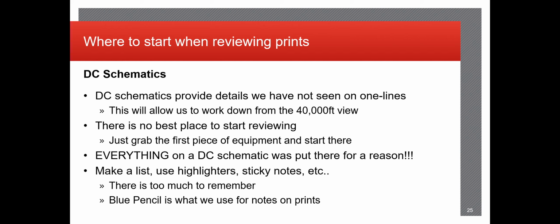When you're verifying the equipment, you don't want someone else to go back and recheck stuff. That's a waste of time, as well as you could miss stuff in that process. So marking up the prints, verifying point-to-points, and when you functionally test, highlighting as well. It saves you in the end and verifies that the equipment was tested properly.